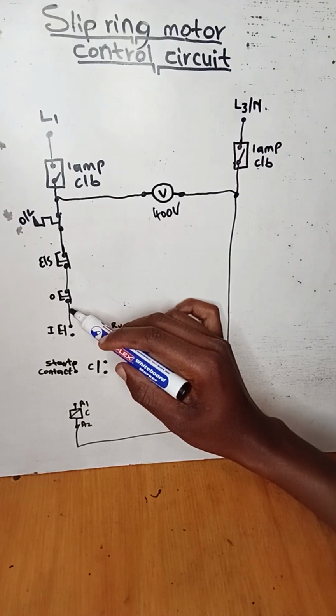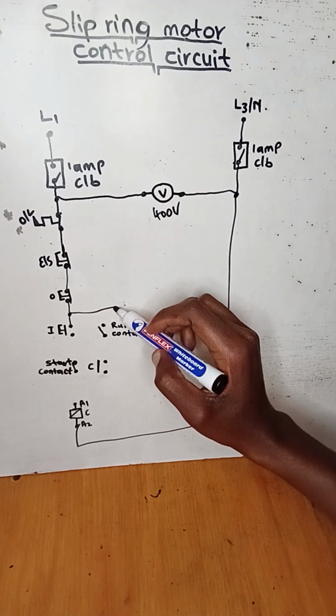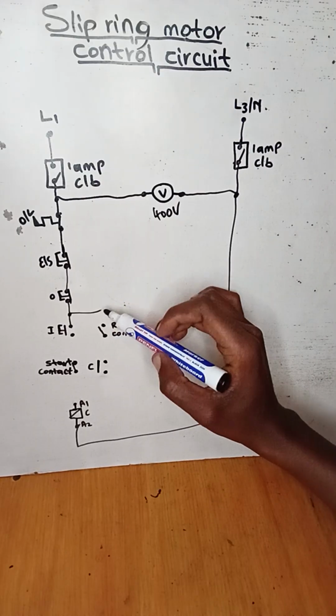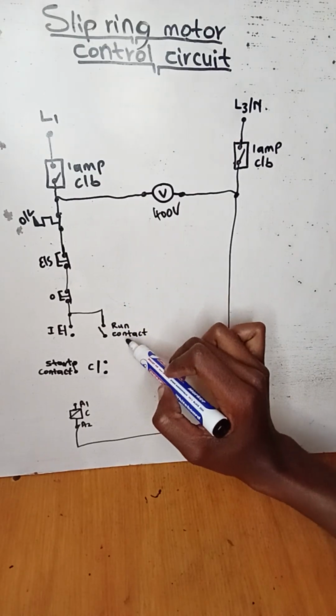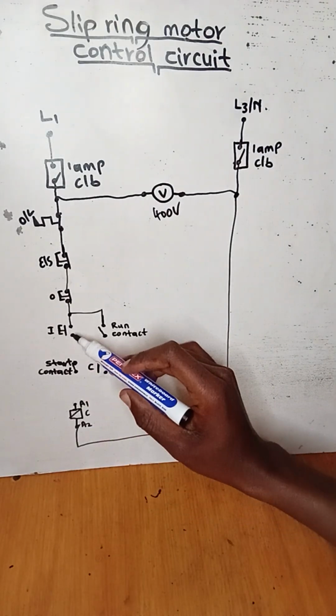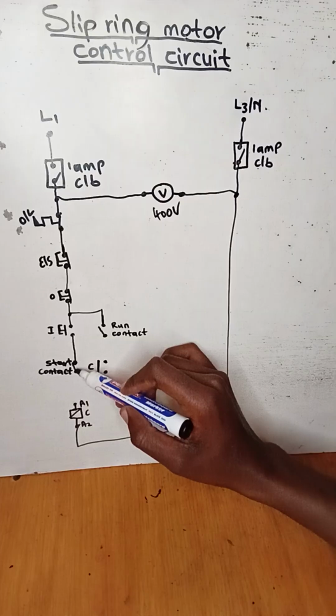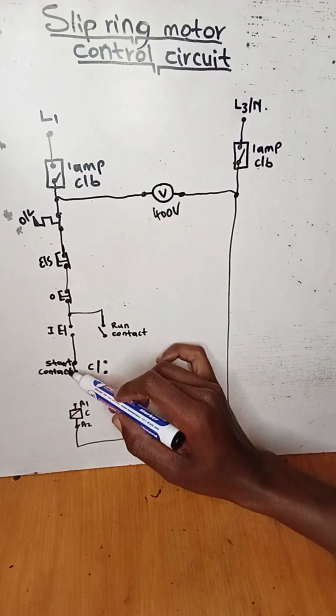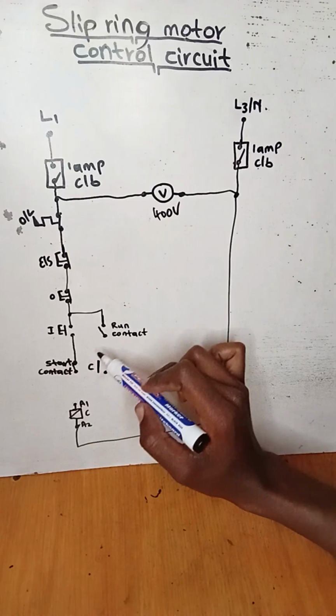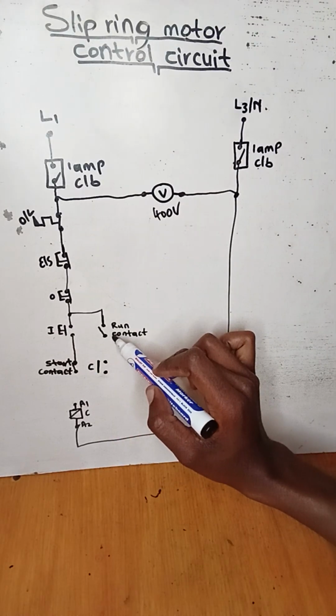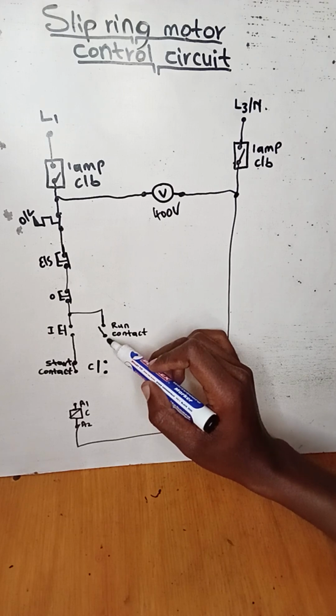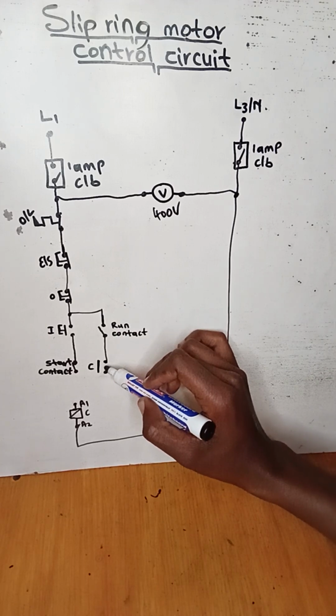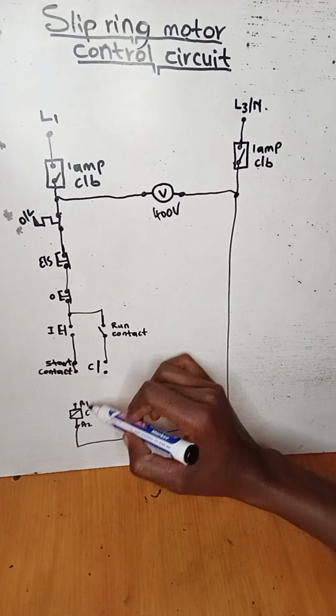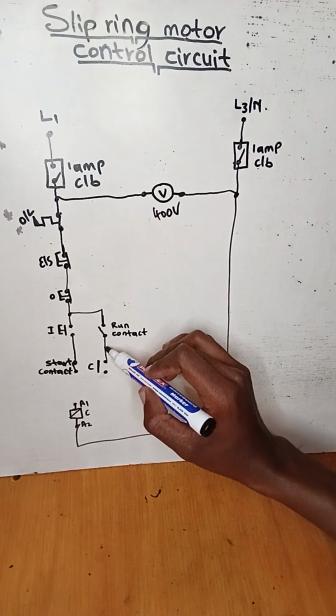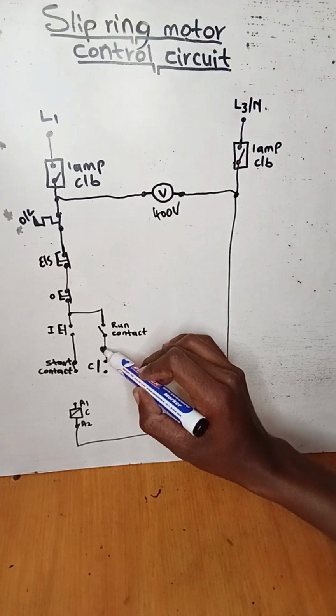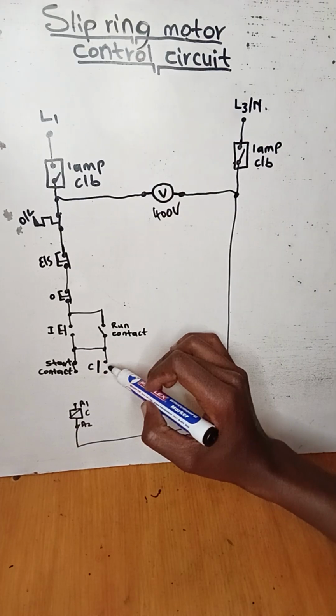before the start button and after the stop button, the wire will be looped to the normally open contact of the run contact, and then after the start button, it will be connected to the normally closed contact of the start contact. So we have the start contact and the run contact, and after the run contact it will be connected to the normally open contact of the retainer of the coil of the contactor, and also it will be looped.